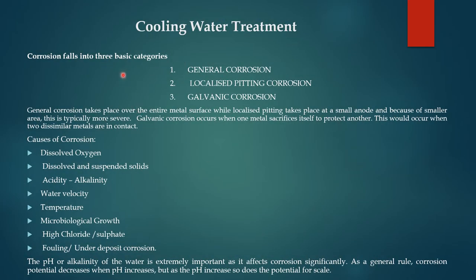If the cooling water treatment is based on corrosion, corrosion falls in three basic categories: general corrosion, localized pitting corrosion, and galvanic corrosion. General corrosion takes place over the entire metal surface. Localized pitting takes place at a small anode and because of the smaller area, this is typically more severe — pitting will be more severe than general corrosion.